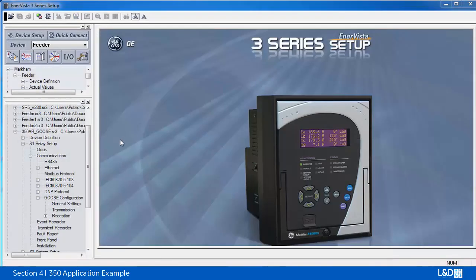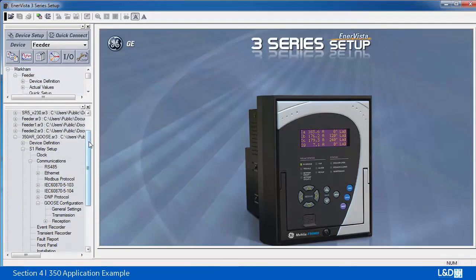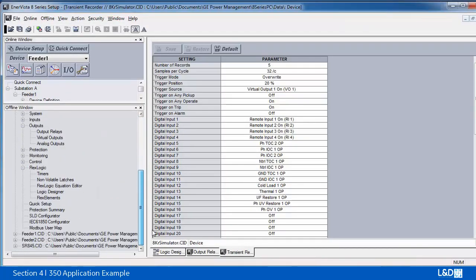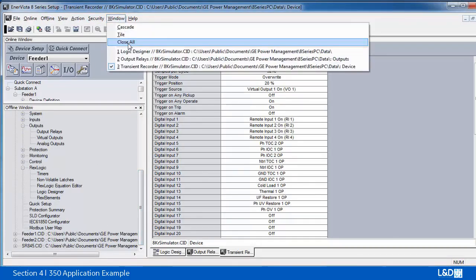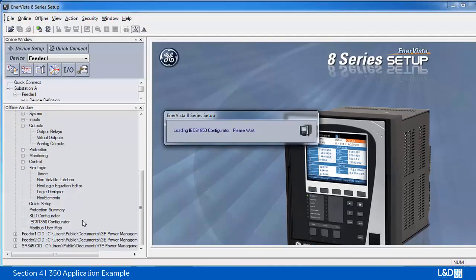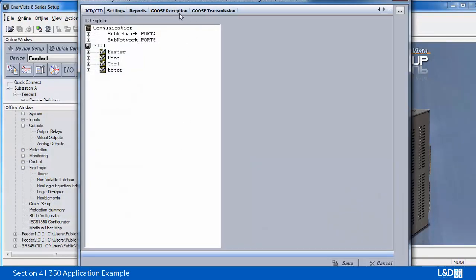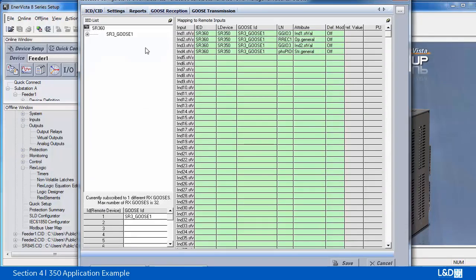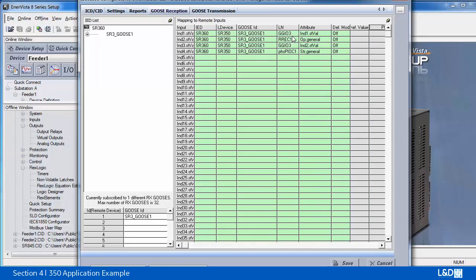Now we go back to the 3 series. In the 8 series, we also need to import the CID file from the 3 series, which is under the 61850 configurator. From the goose reception, we already received the goose message, which I renamed to SR360. That's the goose published from the 350: GGIO3 virtual input 1, reclose RREC1, GGIO virtual input 2, and phase IOC pickup. So this will be received by the 8 series and used as its remote inputs.